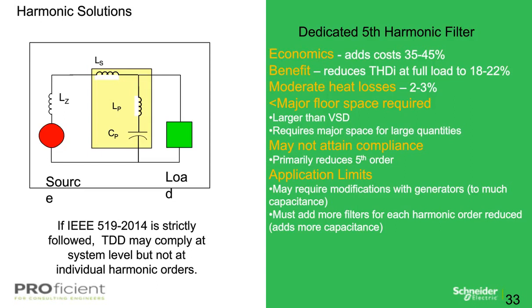And some of the application limits we see are possible generator issues due to high capacitance in the filter, whereas they need to add more filters for each harmonic order. So essentially adding capacitance. And if you look at IEEE 519 as strictly followed, you'll see some of the harmonic orders past the 5th and 7th will not comply per the standard.